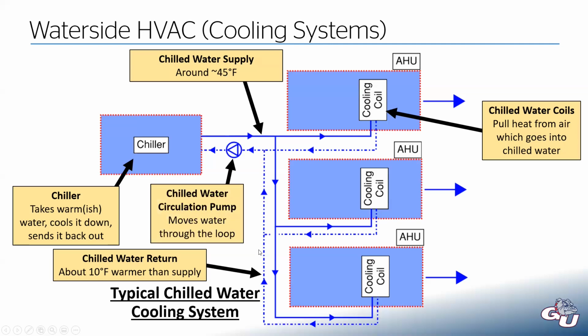That triangle in the circle, again, that's a chilled water pump that represents diagrammatically a pump in our system with the direction of the triangle indicating the flow direction. We end up back at the chiller where we chill it down again and then we send it back out, and you just have this cycle. Fundamentally, this isn't very different than a hot water system. It's just we're moving chilled water instead of hot water.